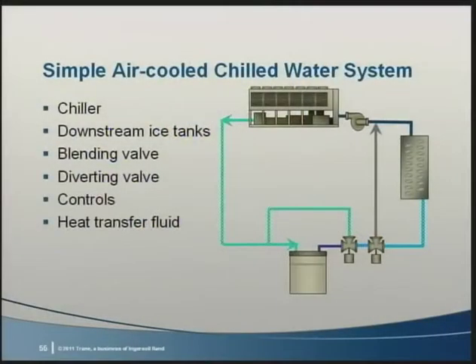Now, another reason why ice is a great system modification for air-cooled systems is because these systems are often smaller, making it simpler to add ice in an easily controllable way. Because air-cooled is likely a positive displacement chiller, we put the storage tanks downstream of the chiller. The chiller receives the warmest entering fluid temperature and produces a higher leaving fluid temperature than it would if the chillers were downstream. The downstream tank location increases efficiency and capacity for positive displacement chillers.